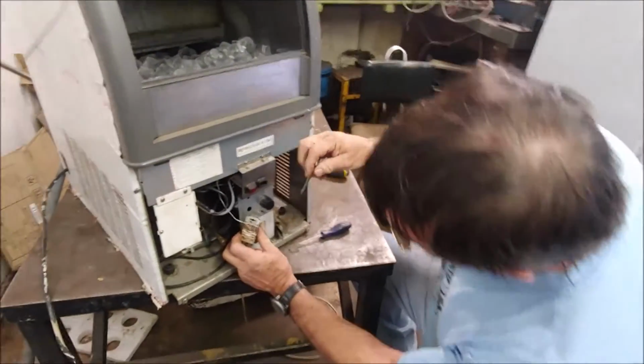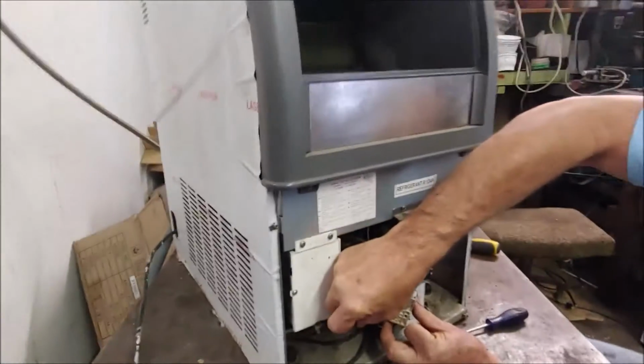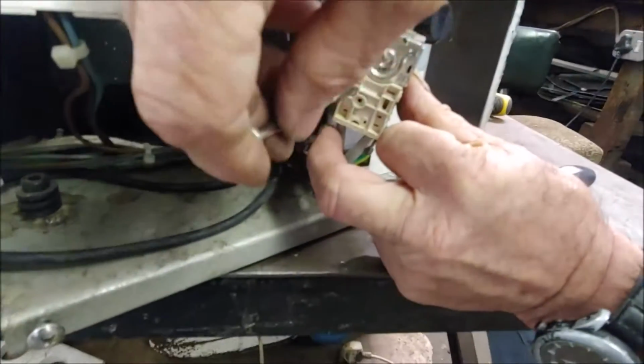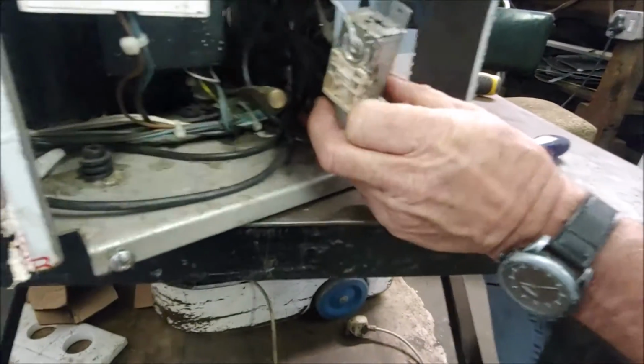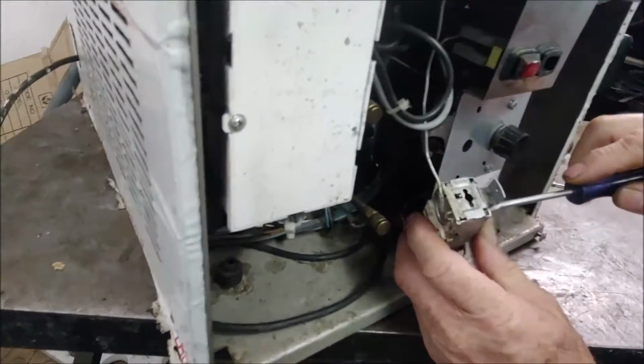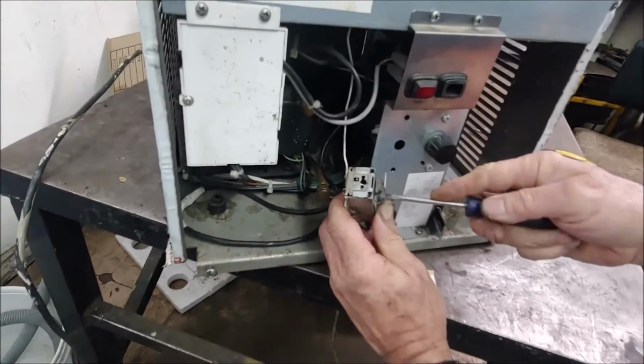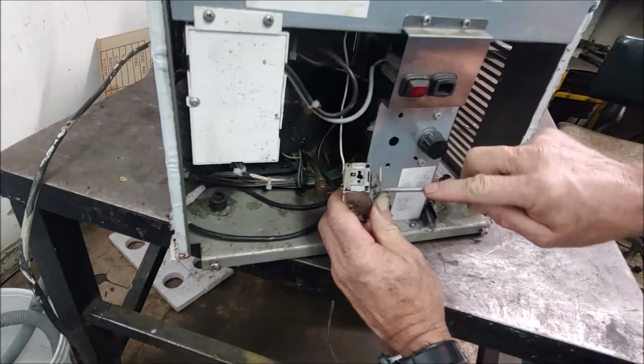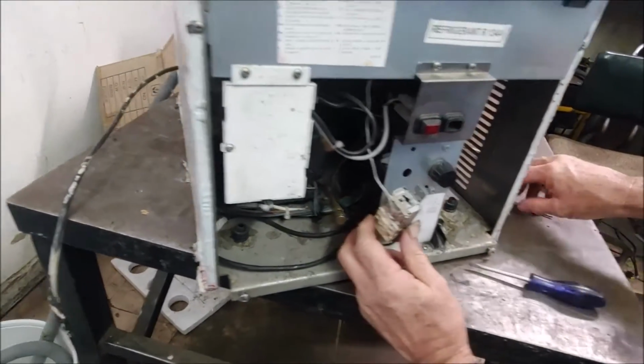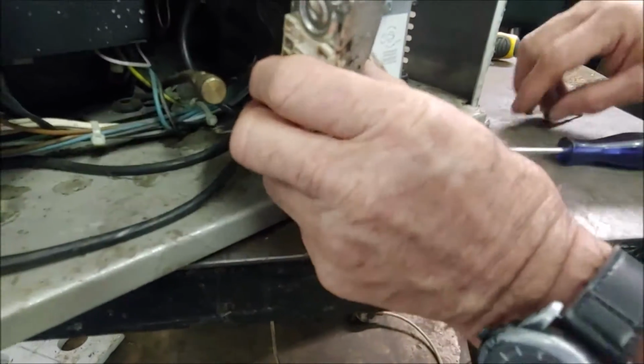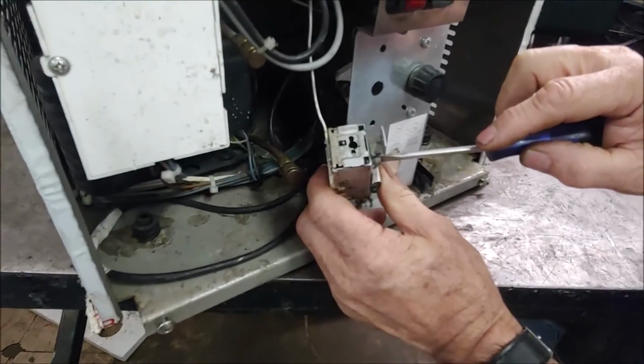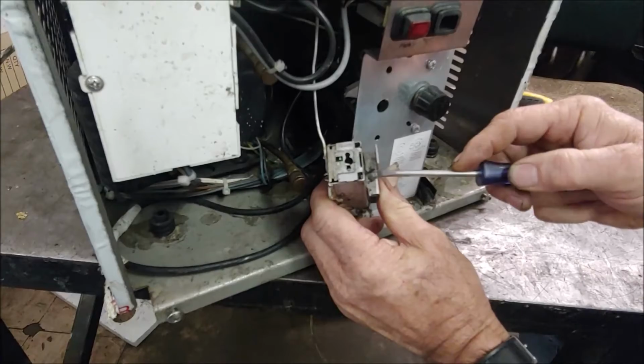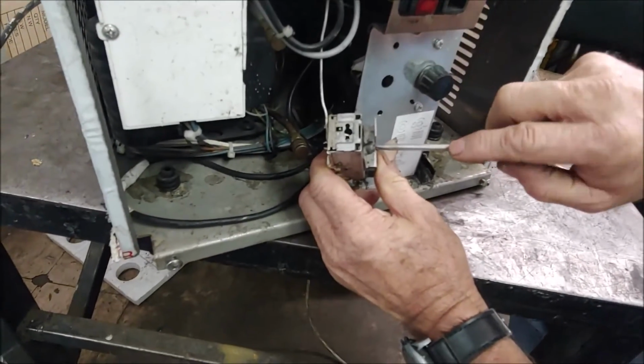Now to adjust the differential, there's a screw behind here. By turning it in, you make the differential shorter - in other words, the position between the click on and click off gets less. Now we're down to about a quarter turn, and you can go a little bit further, turn it a bit more, and make that distance slightly shorter. So there's a shorter differential.